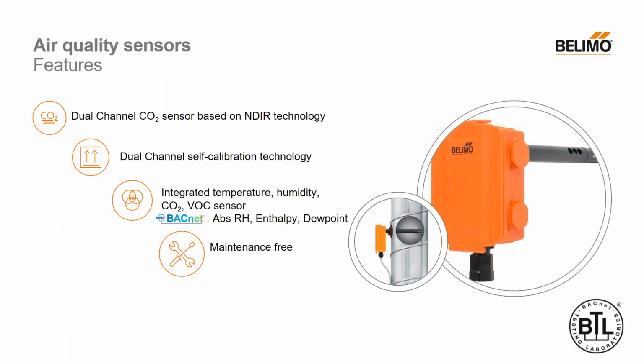When it comes to IAQ, first here we'll talk about our duct mount indoor air quality sensor. One thing all of our CO2 sensors have is something called dual channel CO2 calibration, and that's all based on NDIR technology. So we'll get a little bit in the weeds here on the technology. The dual channel CO2 calibration works with two CO2 sensors. So there is one CO2 sensor for measuring and one CO2 sensor for calibrating in the sensor housing. So periodically that sensor compares the measured value to the calibration sensor and then adjusts accordingly.